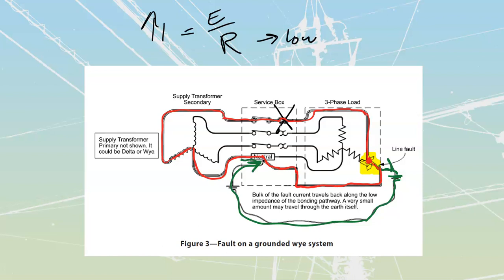It's the whole point of our grounding and bonding systems. We are supposed to ground our system at only one point. So only one point in our system is allowed to actually be attached down to ground itself. I'm just going to erase all of these over here. We have got two options for that, though. This can happen either at the transformer or at the service box. CEC 10206 requires that ground to happen.